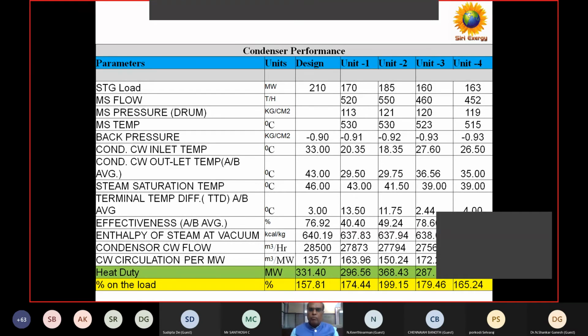Similarly, regarding some pumps and energy efficiency, people had stopped certain fans in winter because of favorable conditions. We told them the fan capacity is only 110 kW, so they stop that 110 kW, but it affects the basin temperature. We told them don't stop the fan—you may operate one more fan and we can show an improvement in the overall turbine heat rate. Though there's extra consumption of 1 kW, it gives a heat rate improvement. So those things we showed.